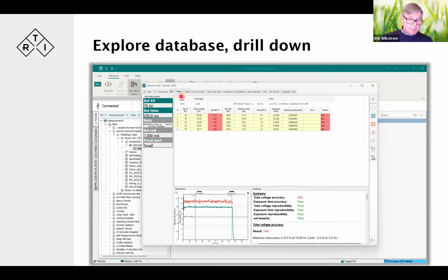In this template, what do we have? This template has a combination of, I don't know, four to six different tests, and one of them, tube voltage accuracy, has failed for us. The other ones passed, they're okay, but the tube voltage failed. So we can go back and get a better understanding of what's going on, and draw conclusions from that — seeing where it was and when it was performed.